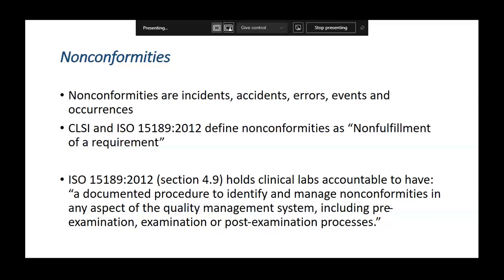As per clause 4.9 of ISO 15189:2012, there must be a documented procedure to identify and manage these non-conformances in any aspect of the quality management system — whether in the pre-analytical, analytical, or post-analytical phase. Clause 4.9 is where RCA is required for any non-conformance or deviation. Clause 4.10 says corrective action must be implemented.